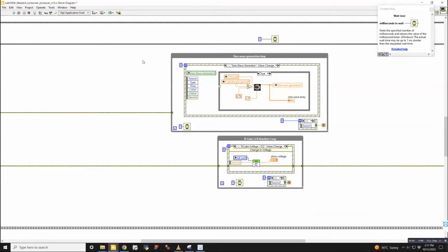So in terms of LabVIEW programming or in general, if you use the instrument default, are you still running into problems due to all the complexity it has, or is it mostly the programming in LabVIEW? Yeah, the more features a spectrometer has, the more complicated it is to run in LabVIEW. I could set it up so that the PI spectrometer is as simple as the Wasatch spectrometer by not giving you access to all the features in the LabVIEW interface that it's capable of changing. I could choose not to integrate the different grating control into LabVIEW, or I could specify that the center wavelength is always fixed at exactly the same place, which are things that are fixed in the hardware of the Wasatch system, but are flexible for changing in the Princeton Instruments system.